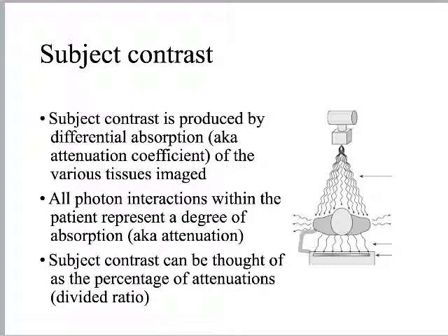beam. Okay? Now, these are some terms that will be used interchangeably, and you'll notice I'm using different language to describe this, so I'm going to be really clear on the language that I'm using. Right here I've got the primary beam. It's the stuff exiting the tube incident on the patient. Down here I have the secondary beam. It's what is leaving the patient, right? And within that secondary beam is where subject contrast lives.